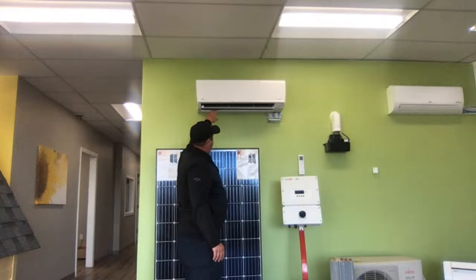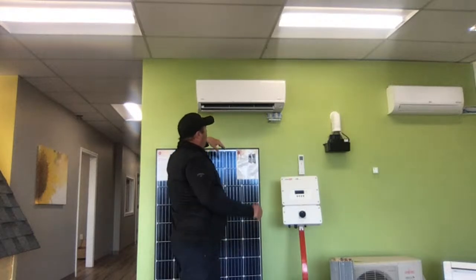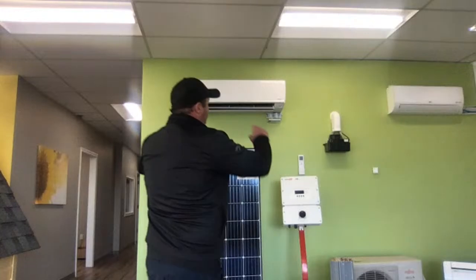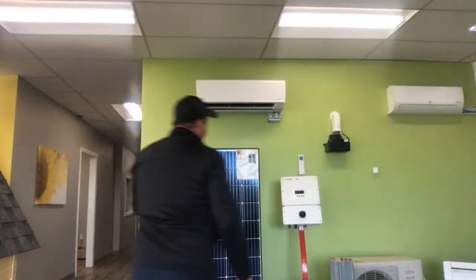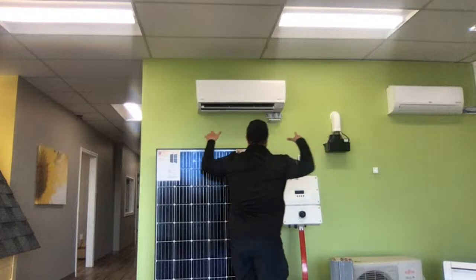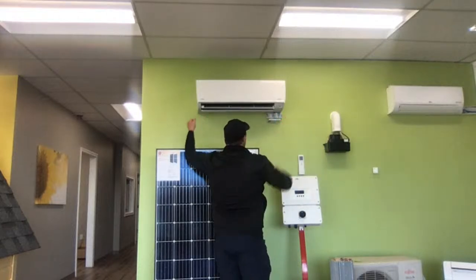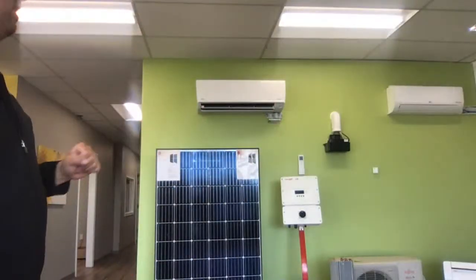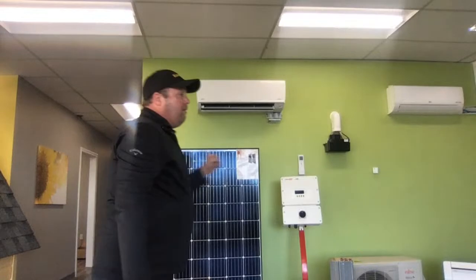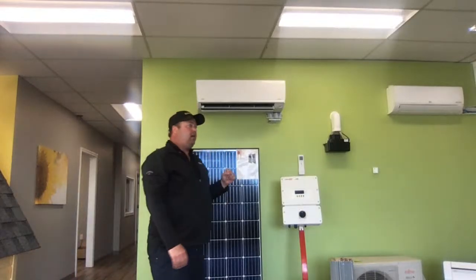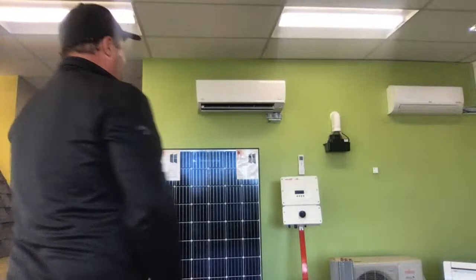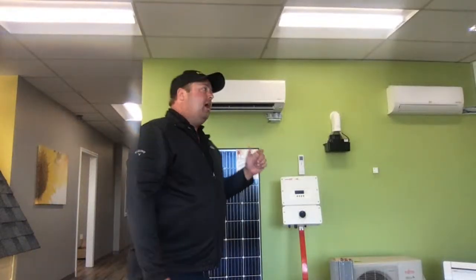And then there's your fan behind here with the louvers. Once every year or two, we come out, take the casing off the head, and put a bib up underneath. We actually power wash the inside of the machine, the fan, and everything. If you've had a heat pump for 5 or 6 years and never had it cleaned, and you use it for air conditioning, you'll be disgusted with what comes out of that thing. It's like a black putrid mess. So yes, you definitely want to get those cleaned every once in a while.